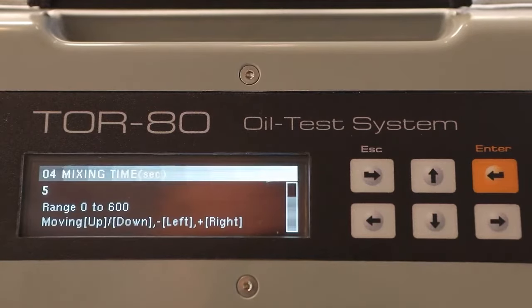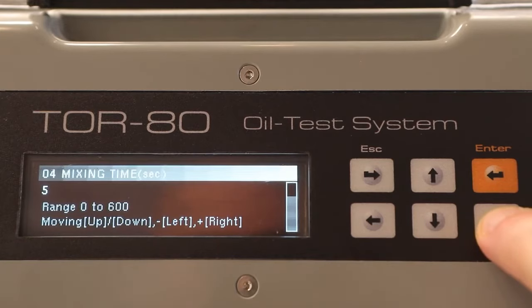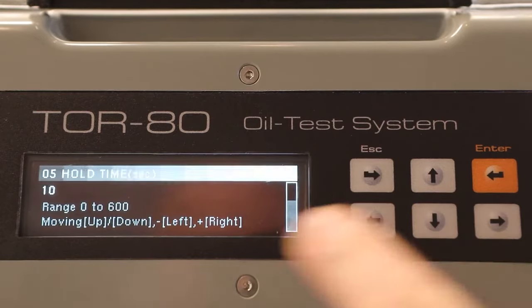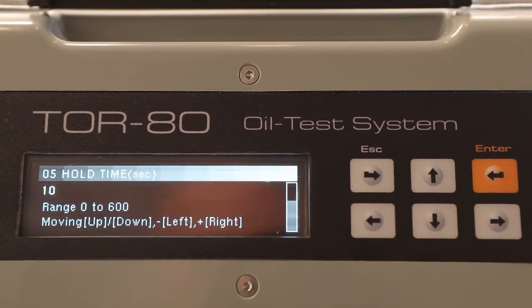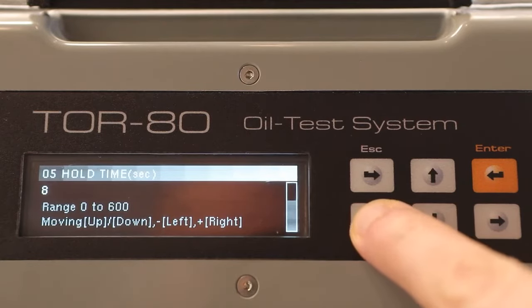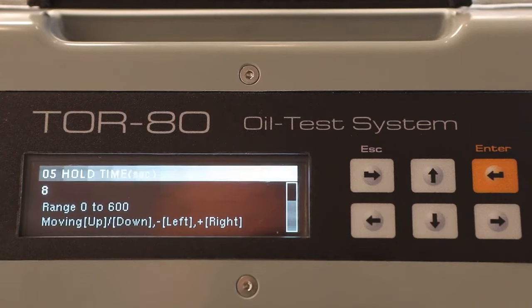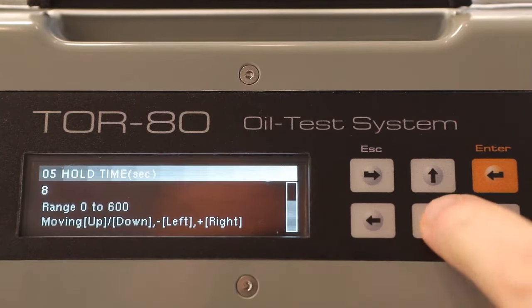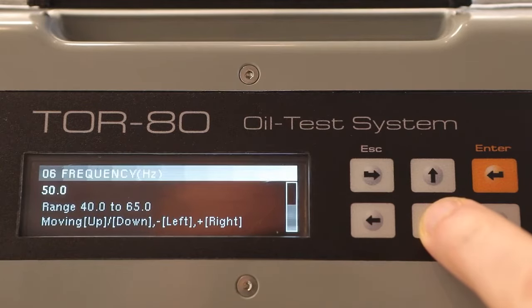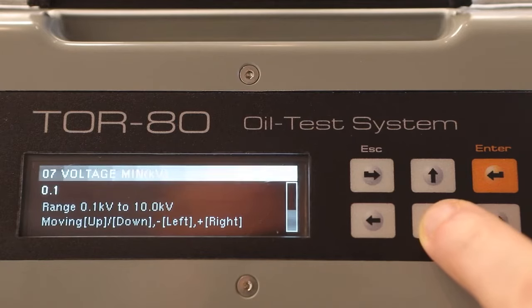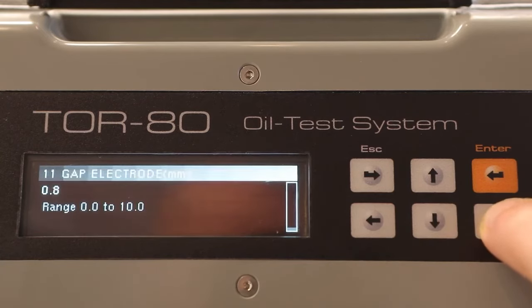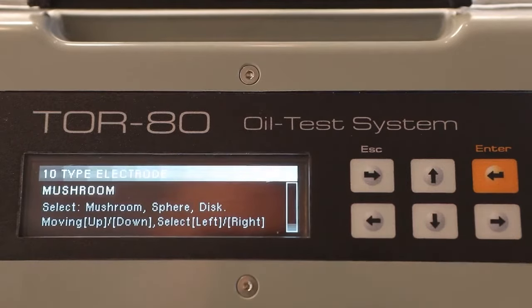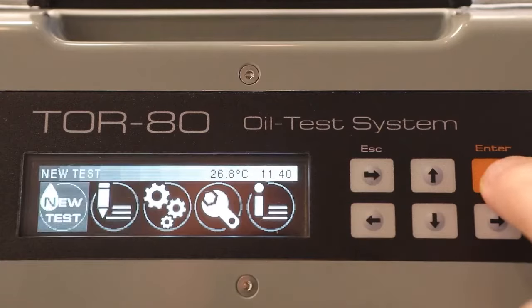The first setting is the number of breakdown voltage measurements in one test cycle. You can select up to 8 measurements to be performed. The second setting is the time of stirring the oil in the cell after the breakdown in seconds. You can also change the duration of hold time. This is the time from the end of stirring to the beginning of the next voltage rise. The third setting is the frequency and the limit of the testing voltage in hertz and volts, respectively. The type of electrodes and the distance between them in millimeters are also selectable. For measurements, you can use spherical, hemispherical, or cylindrical electrodes. After that, you can start a new oil test cycle with the new settings.